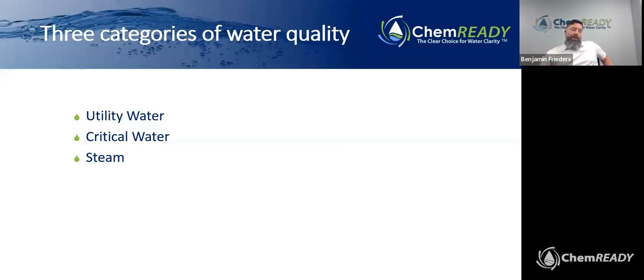The steam from the central plant that supplies heating for, say, HVAC processes, but all other things. Sometimes that steam is admitted to your sterilization equipment. And that steam needs to be monitored for water quality. And then also there are localized steam generators that are standalone, separate from your sterilization equipment that provide steam to those units. So when we talk steam, we're not talking about the steam created inside the sterilizer. We're talking about an external source, external to the sterilization and the final delivery. Some misconceptions we've run across there. So we'll talk about each one of these and how they apply.